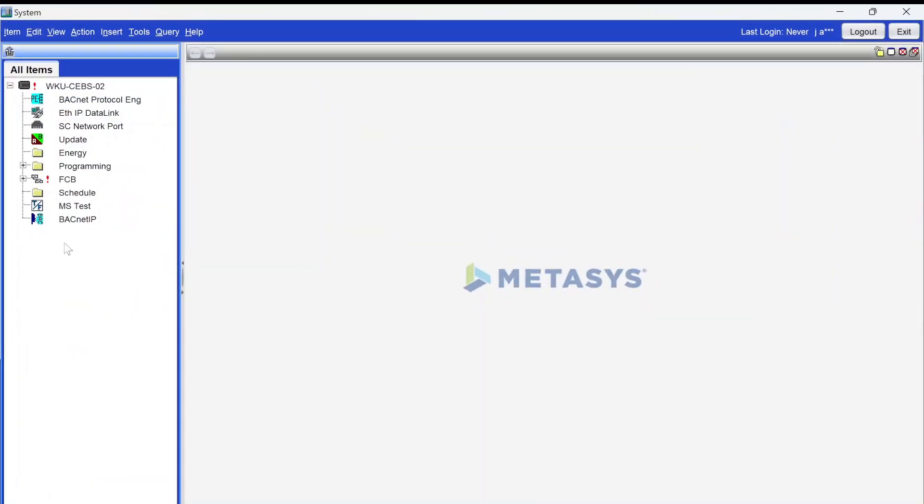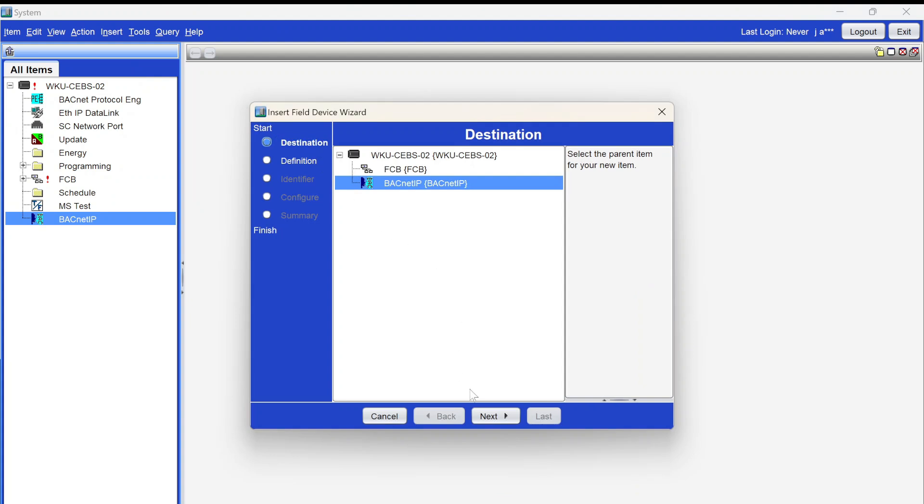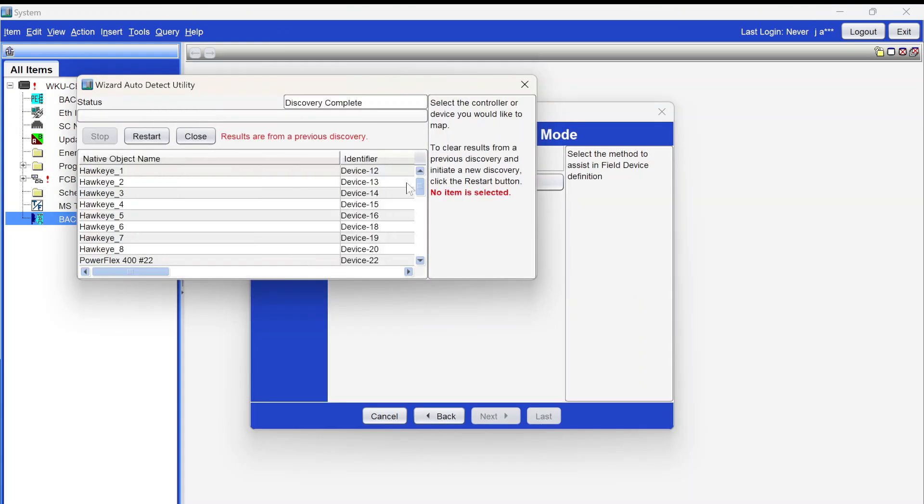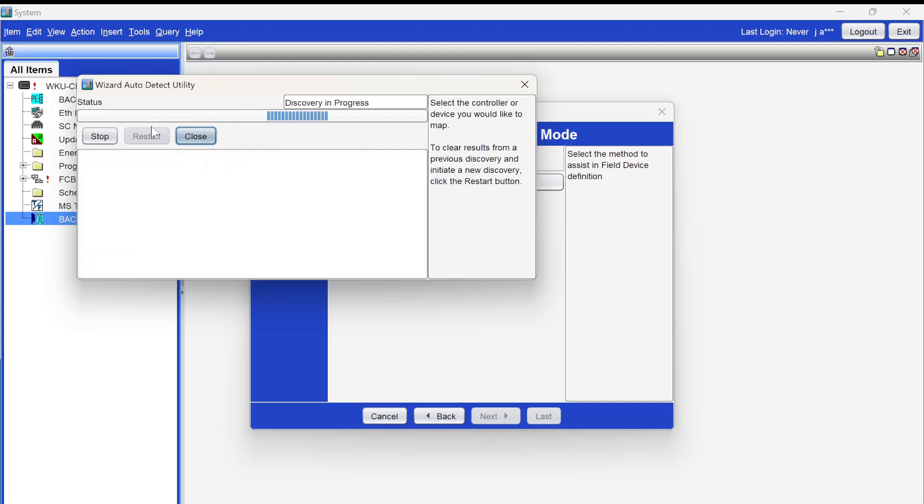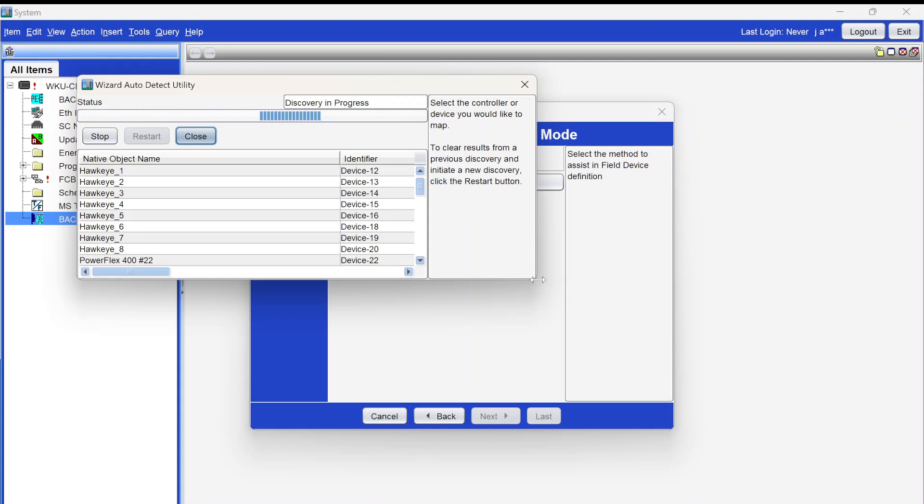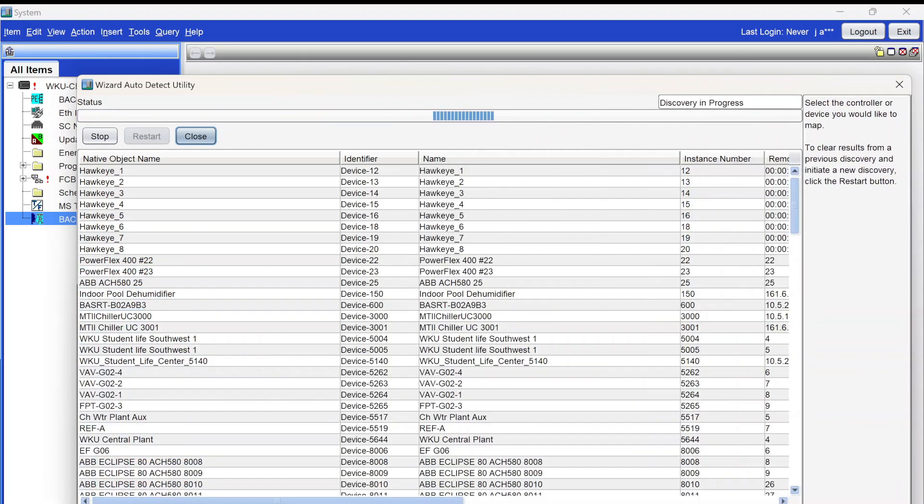We're actually going to be doing this a couple of different ways. The first way I'm going to show you here is by logging directly into the engine. The first thing I need to do is set up an integration for BACnet IP. Go over to my channel, you can see other videos on how to do that. And now I'm doing a device discovery. This is going to go out and discover everything that is connected to our network that is BACnet IP.